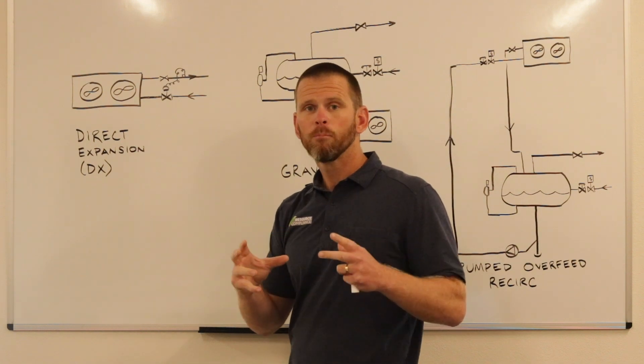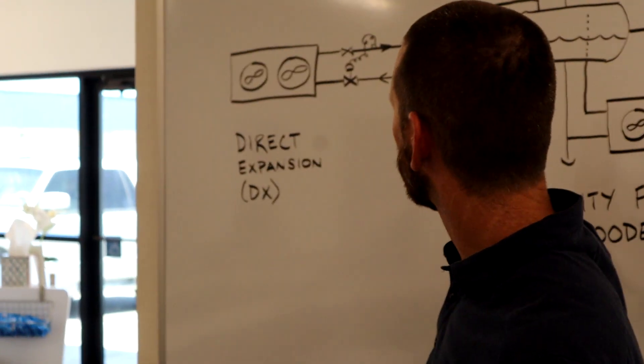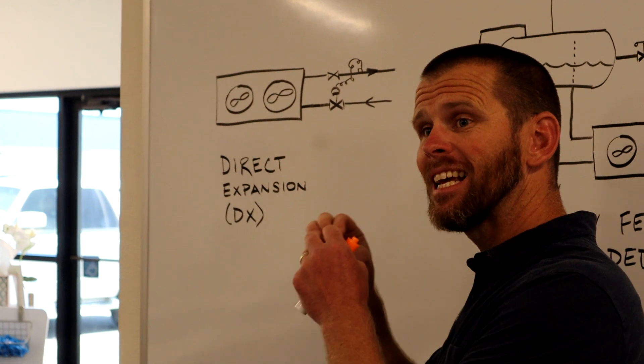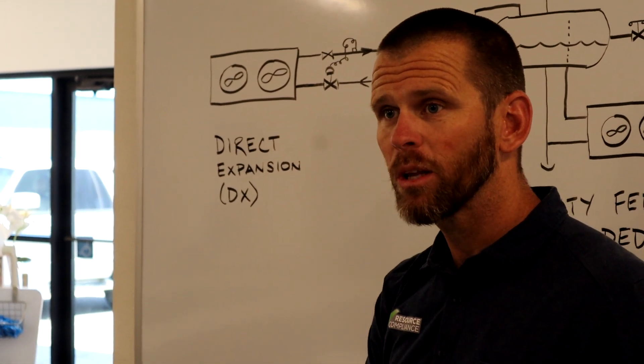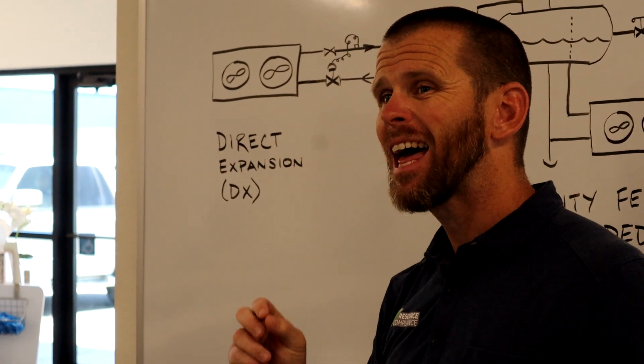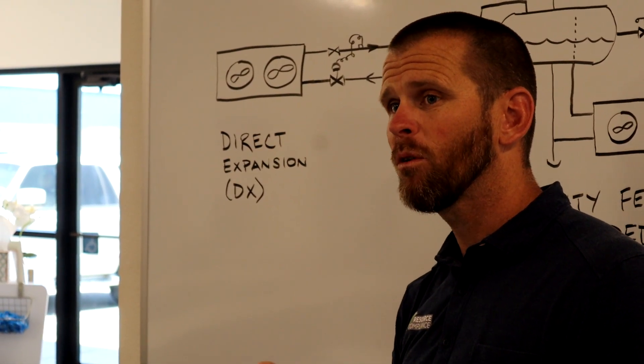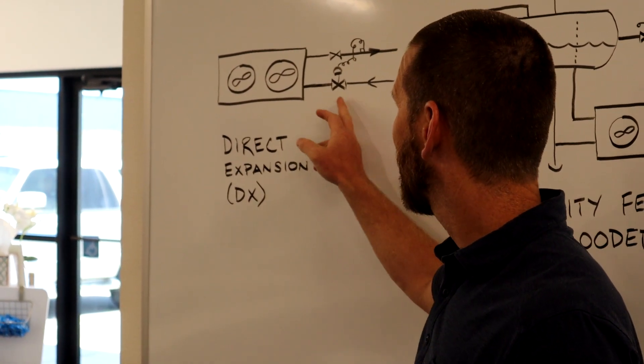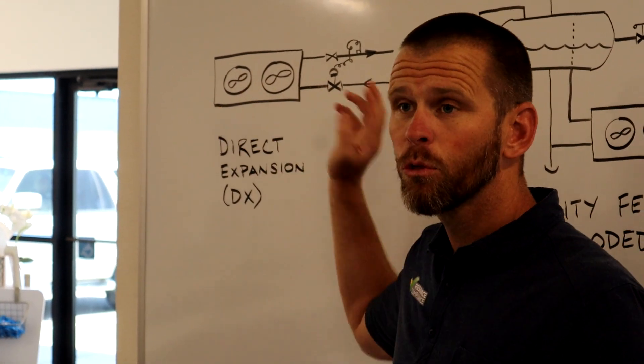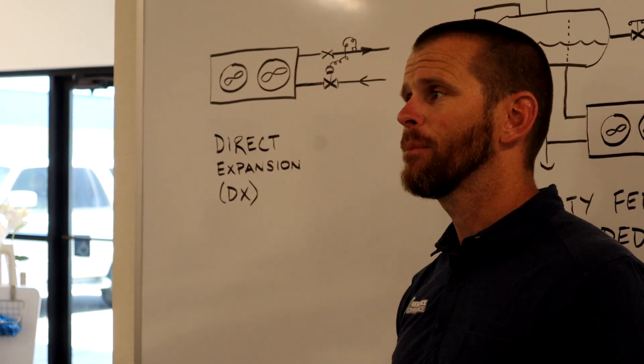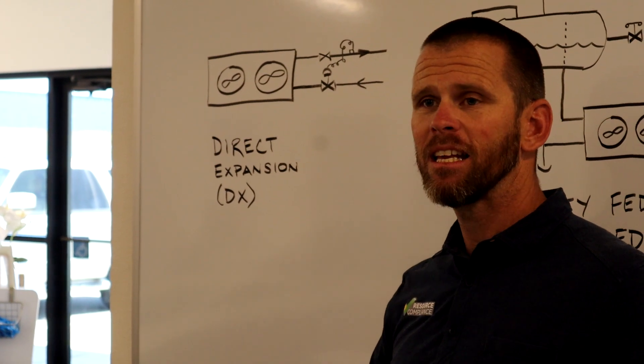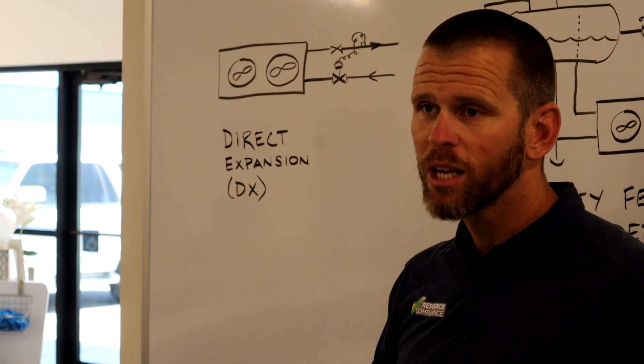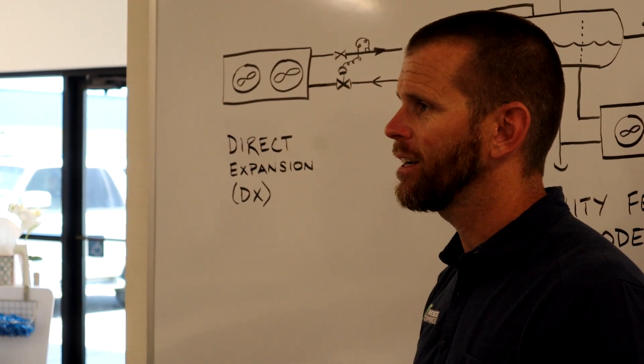However, there is a big drawback. As the high-pressure liquid is expanded and goes to a low-pressure liquid, a percentage of that liquid will flash into gas. That gas has to travel through the evaporator, and it has already given up its refrigerating potential because it has already evaporated.